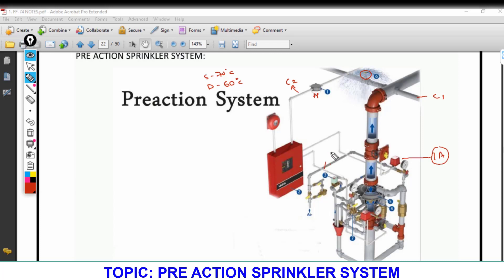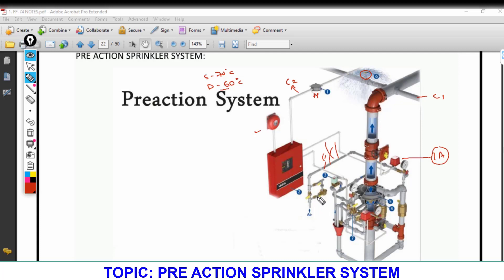If an actual fire occurs, the heat detector — set at, say, 60 degrees centigrade — will sense the heat before the sprinkler bulb breaks, and sends a signal to the fire control panel. The fire control panel activates the main alarm and opens the valve. After the temperature rises a further 10 degrees, the sprinkler bulb breaks, the compressed gas releases, and since the valve is already open, the pump draws water from the tank and supplies it to the affected area.